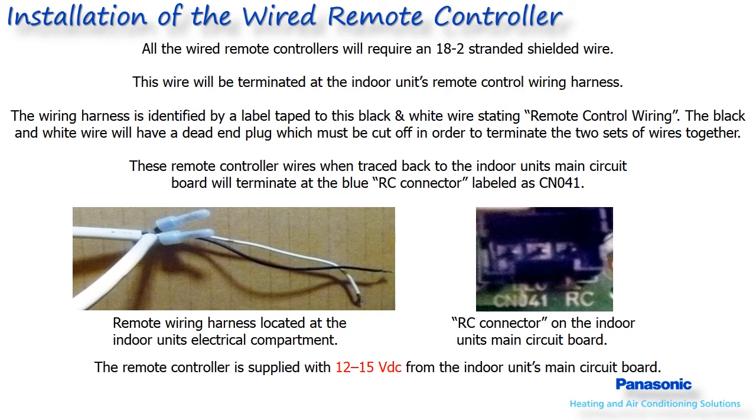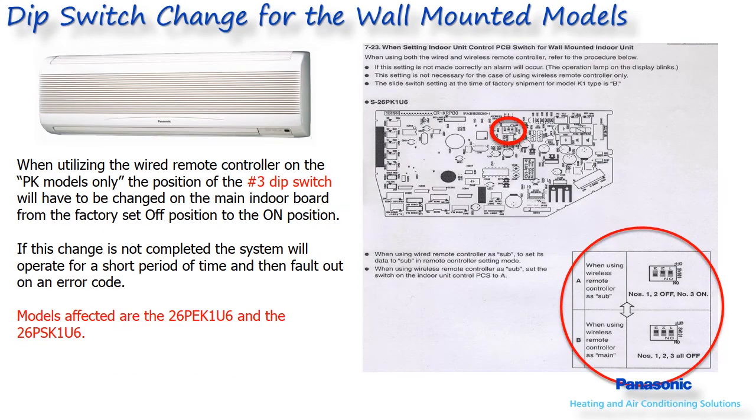These two wires will have a label reading 'remote control wiring.' In the event the label is not present, these wires can be identified by tracing them back from the RC connector on the indoor unit's main control board. Once located, cut off the dead end plug to separate the two wires, then join them with the two wires coming from the wired remote controller. The remote controller is powered from the indoor unit's main control board with 12 to 15 volts DC. When utilizing the wired remote controller on PK models only, the number 3 dip switch on the main indoor board must be changed from the factory off position to the on position.